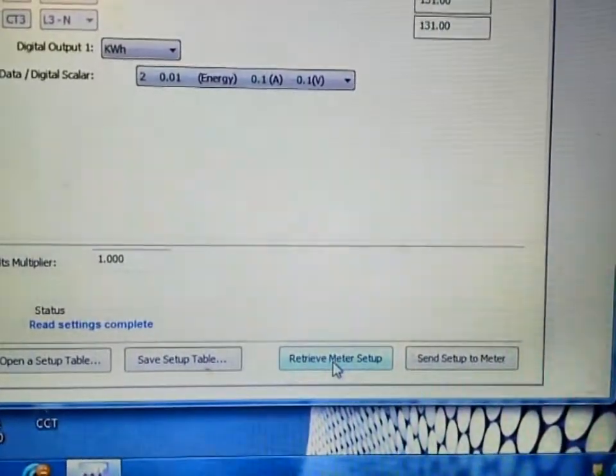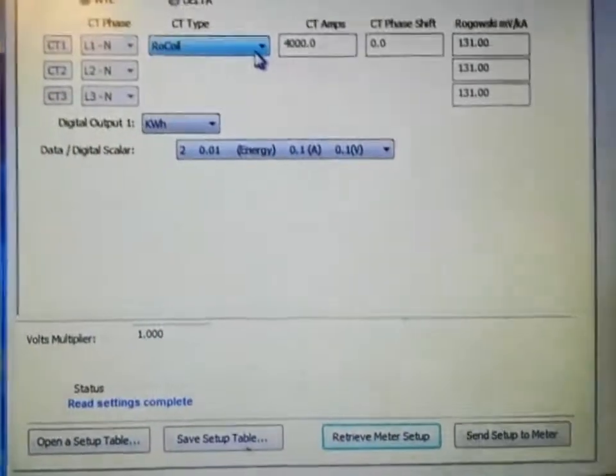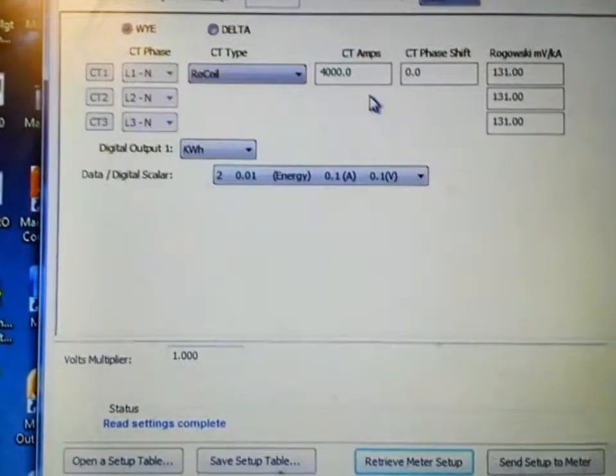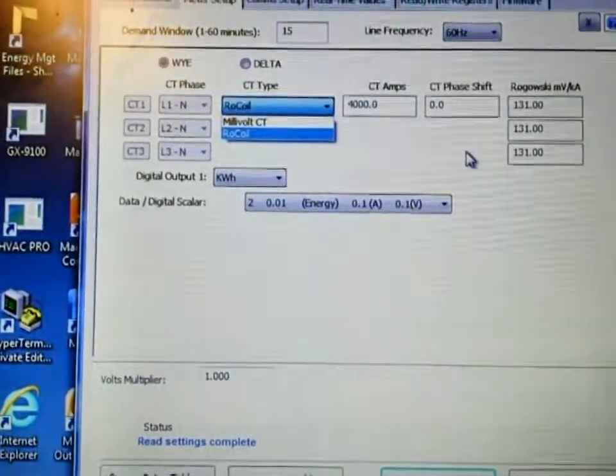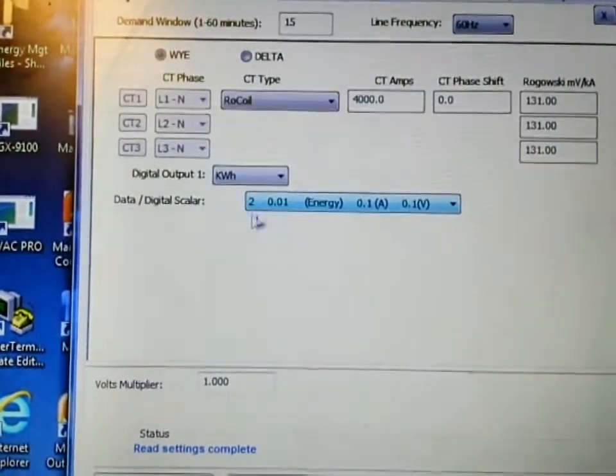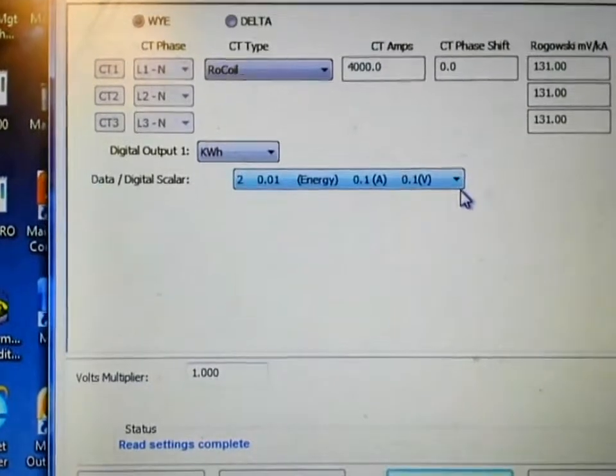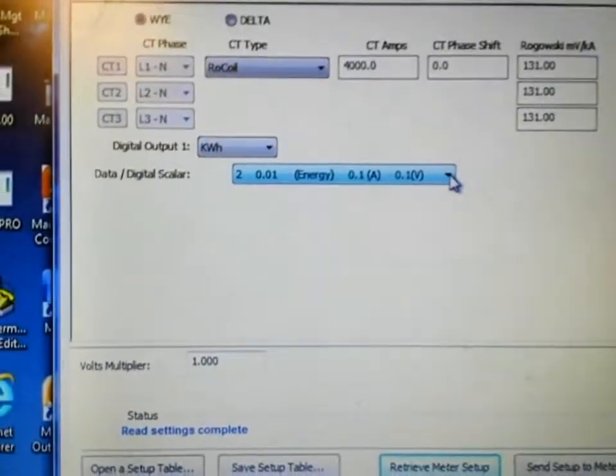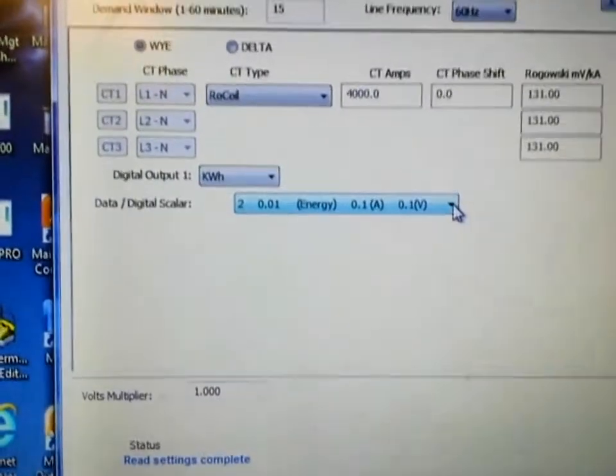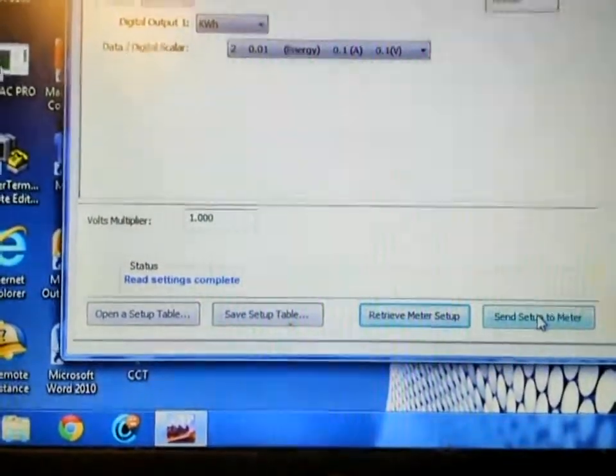It will pull all of the data from the meter. It is in this screen that you will select and configure the CTs for this particular meter. We are using the Rogowski coil CTs, and all of this is pre-configured for us. If you are using one of the other types of CTs, you will need to select that option and then enter the ratio of CTs and all of that information. This particular service is a 400 amp service, and you will select that option here. There is a scaler that you can find in the manual for the various service sizes, and you will enter that value here. Once you have that information configured, you will press Send Setup to Meter and it will send all of that information to the meter itself.